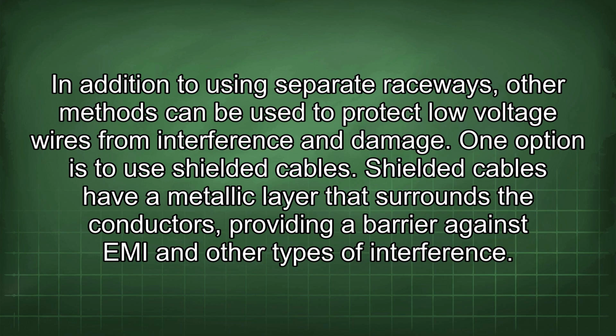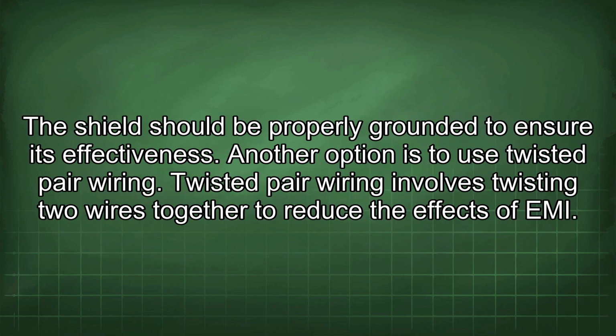In addition to using separate raceways, other methods can be used to protect low-voltage wires from interference and damage. One option is to use shielded cables. Shielded cables have a metallic layer that surrounds the conductors, providing a barrier against EMI and other types of interference. The shield should be properly grounded to ensure its effectiveness.